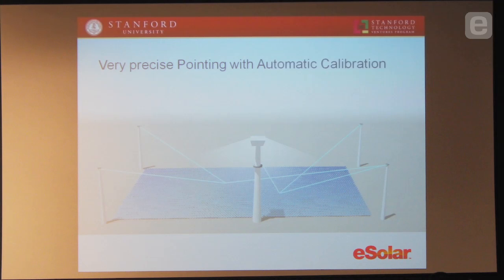Taking advantage of Moore's Law, today you can buy high-resolution sensors. You put them on towers in the corner, and those sensors can look at all the mirrors and detect every single mirror with image recognition — picking out each mirror. With a GPS time clock, you figure out the time of day and where the sun is, look at the reflected beam coming out of each mirror, and in real time compute the angle of every mirror at way higher precision than you ever could by surveying in the past. Now it requires a $2 microprocessor in every mirror, but a $2 microprocessor is now negligible and off-the-shelf — even 10 years ago it would have cost $5,000 per mirror. Today it costs $2. It's just unbelievable what Moore's Law allows.